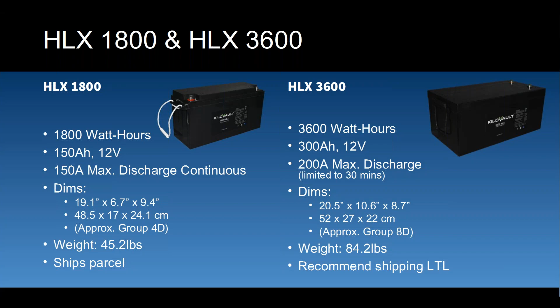So moving on to the design of these battery banks, the nice thing about using a 12-volt battery as opposed to the KiloVault Hab, which is a nominal 48-volt battery, is that it's fairly modular. You could start with a 12-volt battery and a single 12-volt inverter charge controller, and eventually, if the customer needs to expand the system down the road, build up to a 24 or 48-volt battery bank by just wiring additional batteries in series. With these batteries, the maximum bank size we support is 16 batteries, or 4 strings of 4 in parallel.